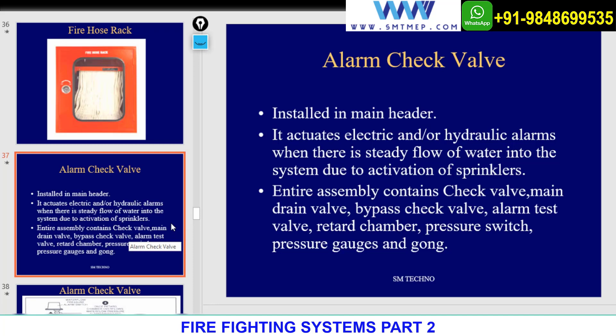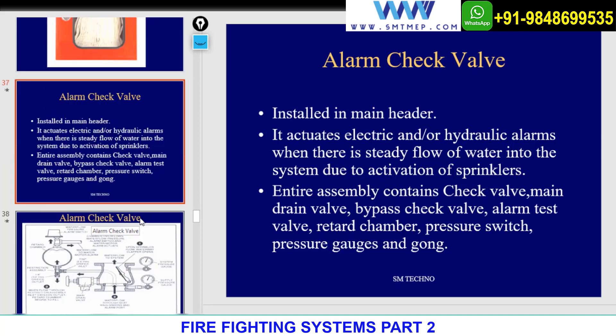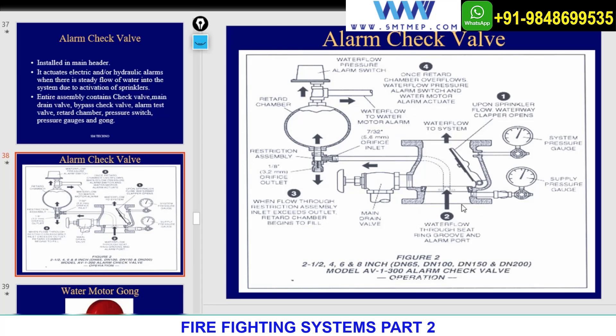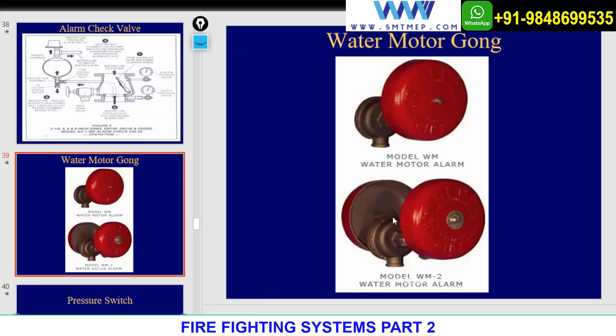The alarm check valve is an assembly containing several other components, which will be discussed in detail with drawings and images. It is found in the main pipe. When water flows, it activates the gong and the system. There are other control systems as well — the alarm check valve is not the only component responsible for activation; we also have zone control valves and pressure systems. The gong is a mechanical alarm that rings like a bell whenever water flows.